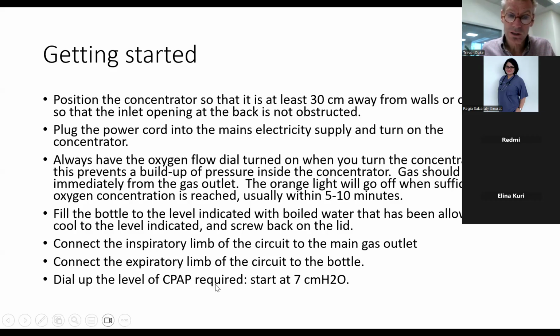And then you dial the level of CPAP required. You could start at 7 or 5 centimeters of water. Before you connect the patient interface, like the nasal prongs, to the patient, always check that there's no bubbling. You shouldn't see bubbling before you connect it to the patient. If you do see bubbling, that means there's auto bubbling, and that means there's a blockage in the circuit somewhere, like there's too much resistance in the circuit or something like that.